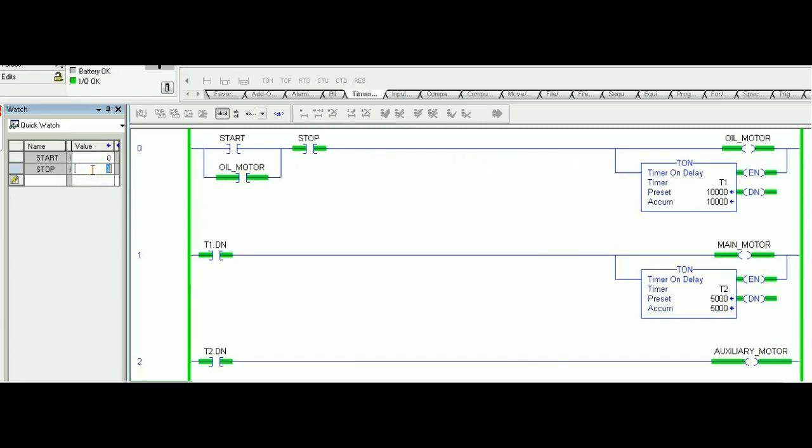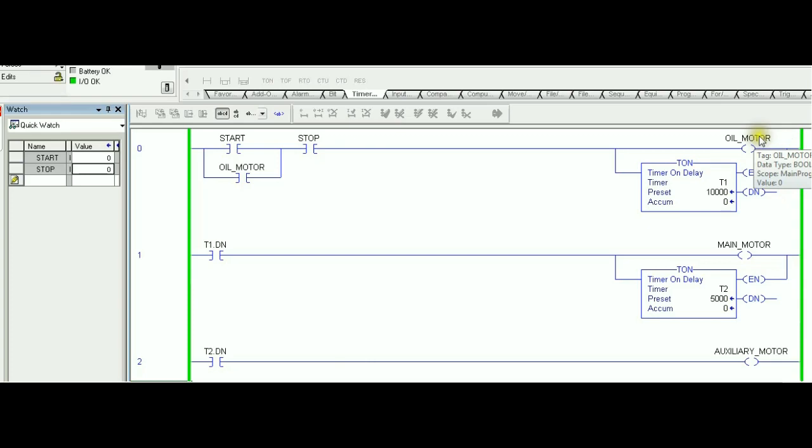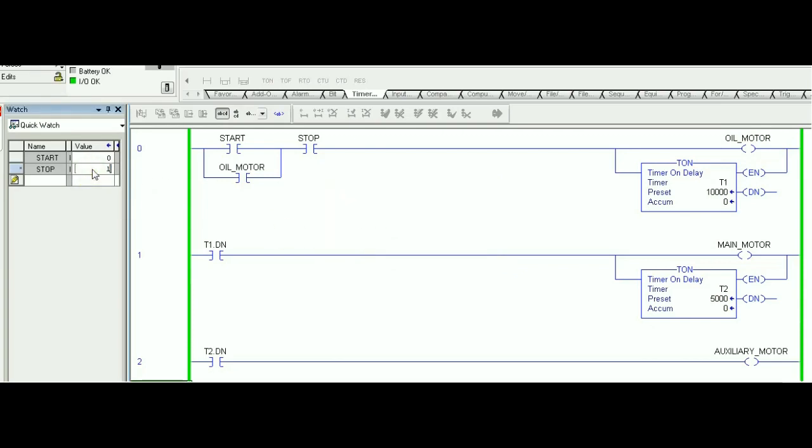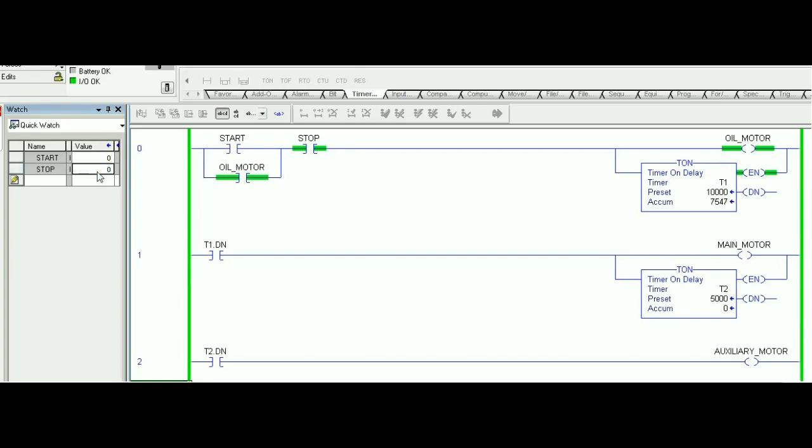Any time you decide to hit the stop. Remember, the stop is a normally closed switch. That's why to the left side of the screen, you see it's reading one into the PLC memory. You press that switch. It will be open. The XIC instruction, this one, changes to false. It breaks the rung. And literally, everything goes to zero. One more time. You let go for the stop. It goes back to the closed state. XIC goes back to true. One more time. If you hit the start right now, in the middle of, right now it's still running. If you decide at that point that you want to hit the stop, it will stop everything right away. So, that's the solution using TON.